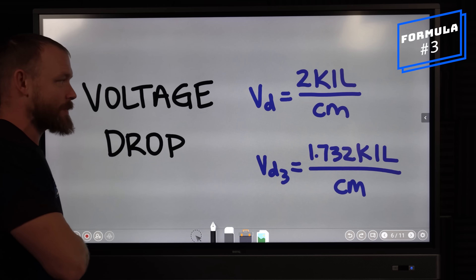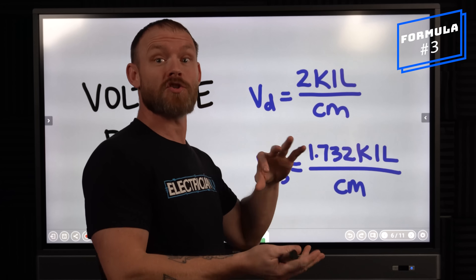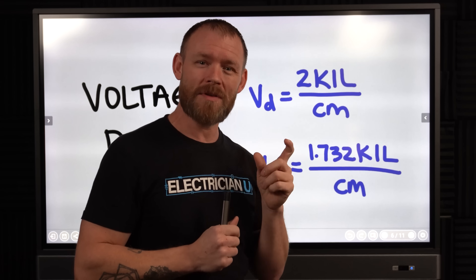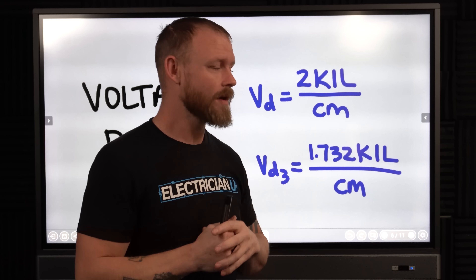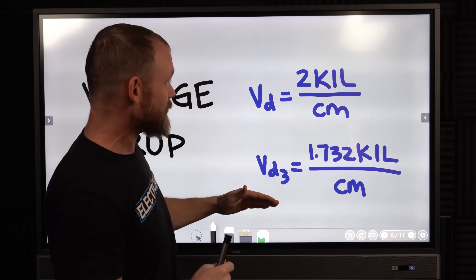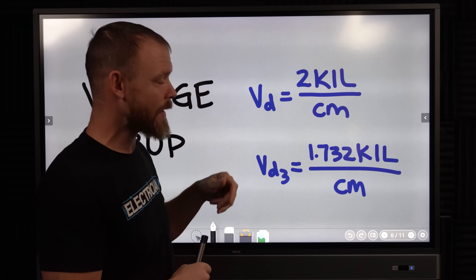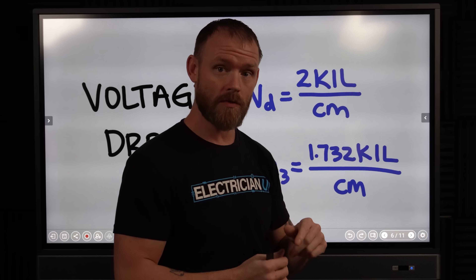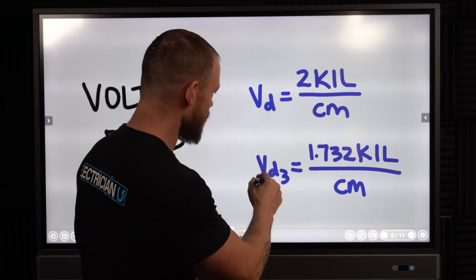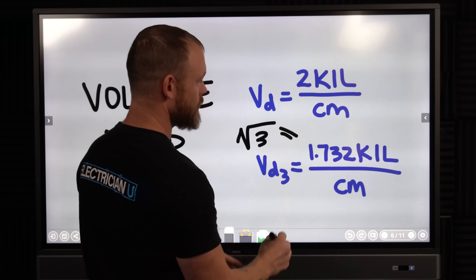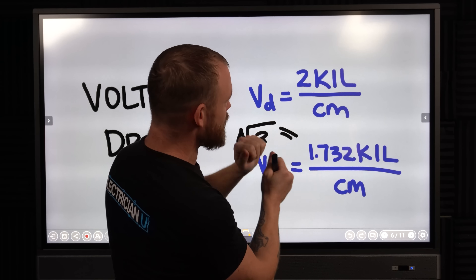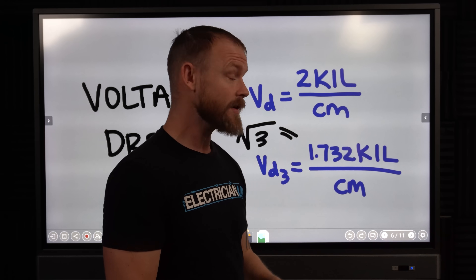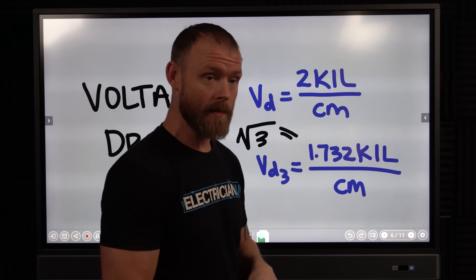Next up is voltage drop, which we'll frequently encounter in the field. You can use Ohm's Law for a rough voltage drop calculation, but it's not very accurate. A better approach is to use the dedicated voltage drop formulas. I have two here: VD for single phase and VD3 for three phase. Any time you do three phase, you have to introduce 1.732 — the square root of three — into the formula. The formulas are very similar; the three-phase one multiplies by 1.732 instead of 2.